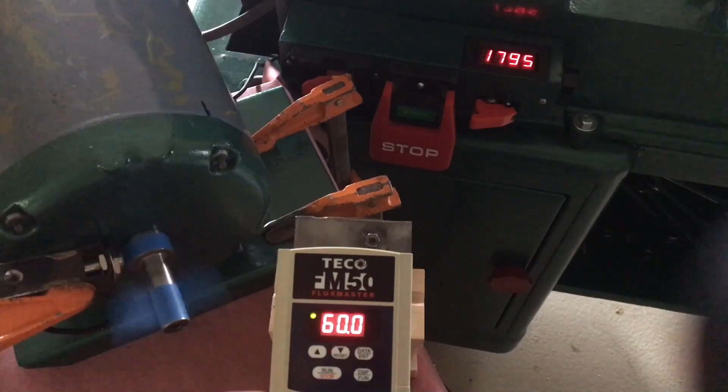The VFD still has all the factory settings except I have already set the maximum at 80 hertz. So at 60 hertz, it's putting out almost 1800 RPMs. You can also see that the acceleration time and the deacceleration time is a factory default of five seconds, which is pretty slow. We'll change that.